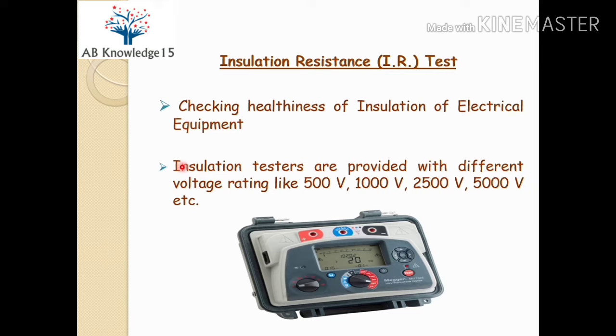For carrying out this test, we use insulation testers. This one is a tester from Megger company. These insulation testers are provided with different voltage ratings like 500 volts, 1000 volts, 2500 volts, 5000 volts, etc. So these are the different options available in this type of insulation resistance meter.